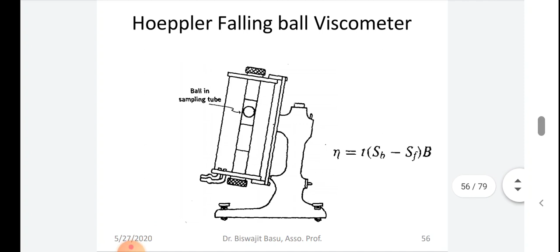Now, depending on the diameter and material of construction of the ball, this instrument can be used over a range of 0.5 to 2 lakh poise. See that range, 0.5 to 2 lakh poise. For better results, select a ball which takes not less than 30 seconds to fall between the two marks. The largest possible diameter ball should be employed.